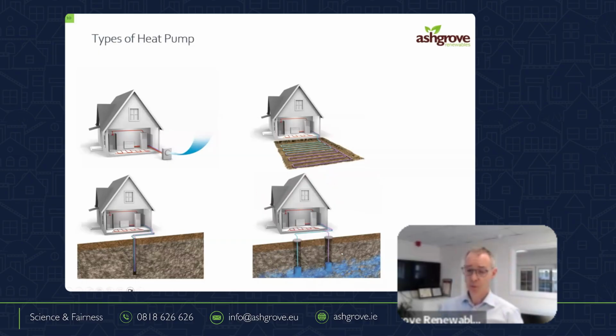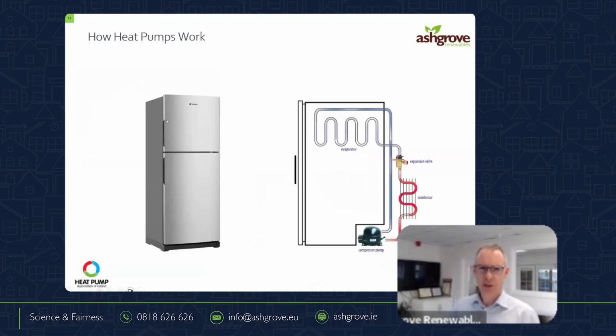But if you're into a bigger system where you do have a regular maintenance schedule, an open loop system, you've very much less, if that's proper English, drilling cost than maybe drilling 20 or 30 or 100 ground loops. If you have access to plenty of water, it's quite cheap. Now, you do have to take into account the running cost of that pump, and you have to make sure it's not too deep, because obviously the deeper it is, the bigger the pump is, and the higher the running cost is. And of course, that all has to come out of your efficiency or your running cost. So that's the types we'll be talking about.